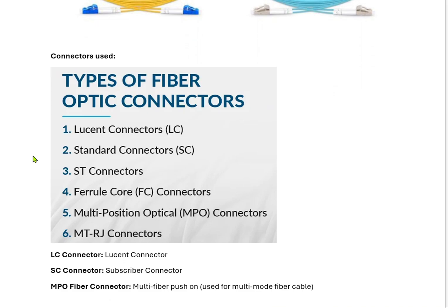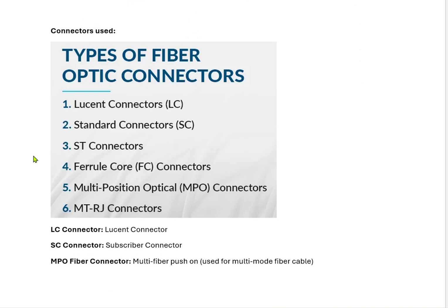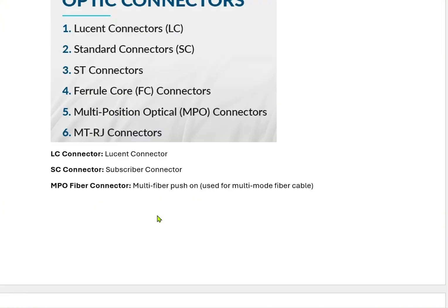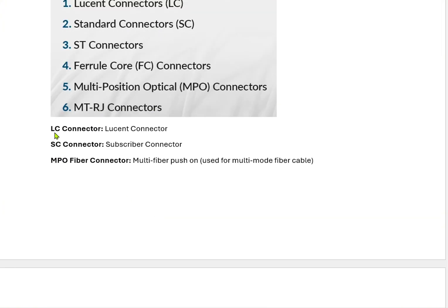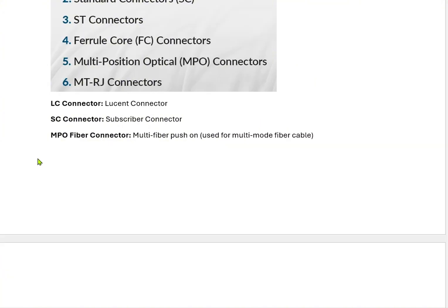There are different types of connectors used in single mode and multi mode fiber cables. The examples are LC (Lucent connectors), SC (subscriber connectors), ST connectors, FC connectors, MPO and MTRJ connectors. Normally we use LC, SC, and MPO fiber cable connectors — MPO stands for multi fiber push on. These MPO cables are typically used in multi mode fiber cables. These are the widely used fiber cable connectors in data centers and in normal use.